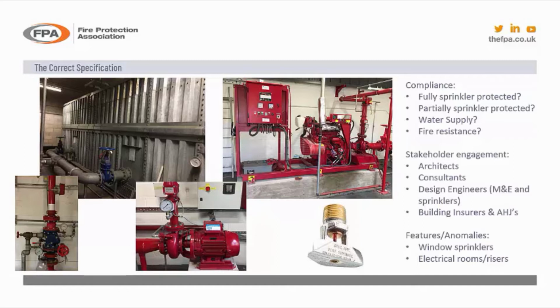Does the water supply fire pumps cater for the height of the building? Has it been properly thought about that maybe the height of the building is over 45 metres and you might need multi-stage pumps, therefore sectionalising your building into different sections so that each section is covered by a classification in terms of height between 0 to 15 metres, 15 to 30 or 30 to 45. And fire resistance, as we spoke about, that's another issue with regards to, like I say, the height of the building and what is required. The difference between life safety requirement and property protection requirement is quite different. So is the system going to comply?